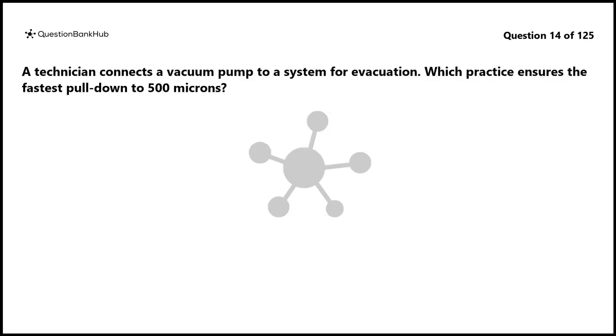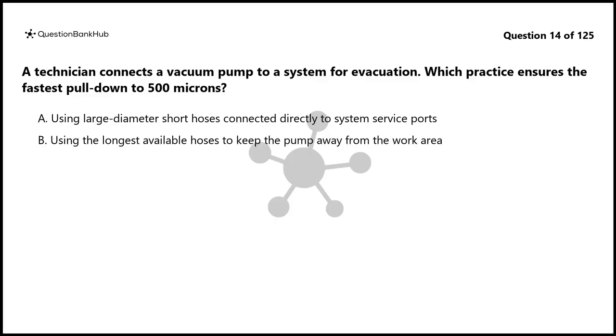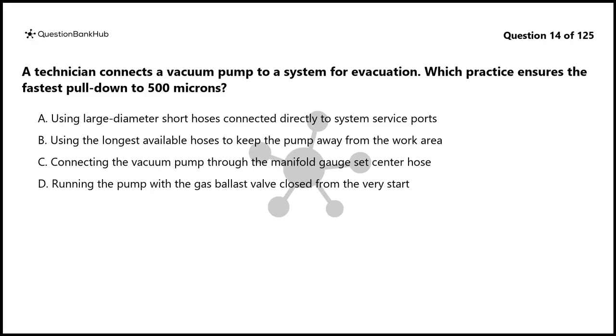Question 14. A technician connects a vacuum pump to a system for evacuation. Which practice ensures the fastest pull down to 500 microns? A. Using large diameter short hoses connected directly to system service ports. B. Using the longest available hoses to keep the pump away from the work area. C. Connecting the vacuum pump through the manifold gauge set center hose. D. Running the pump with the gas ballast valve closed from the very start.